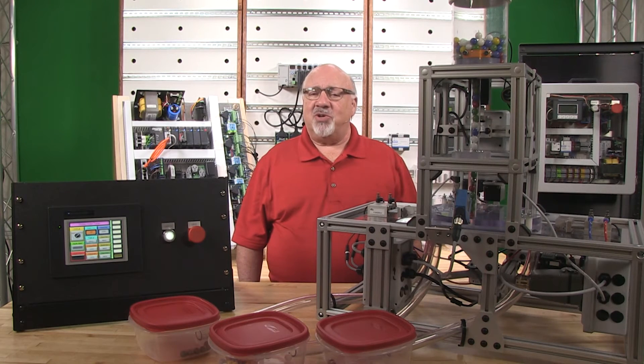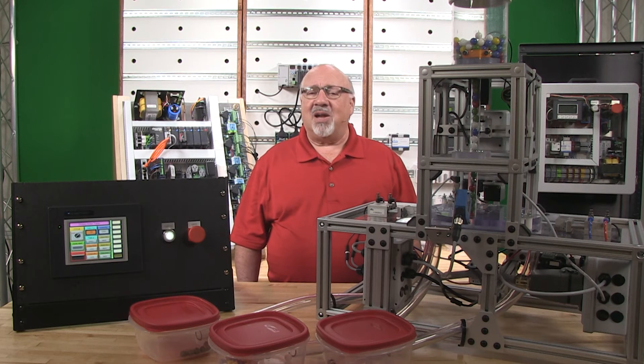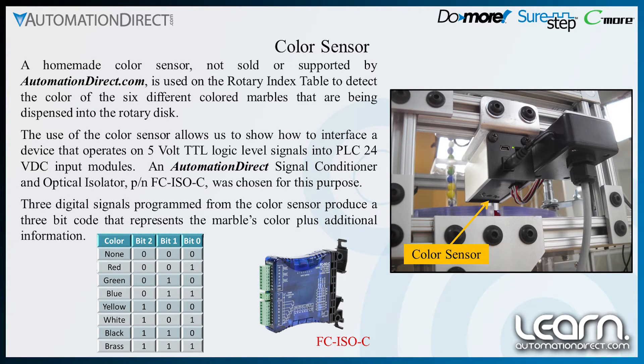The two reject slide cylinders used for the steel and brass balls are equipped with magnetic sensors actuated from the cylinder's magnetic piston. These sensors are used to determine the position of the slide cylinder. The cylinder fully extended sensor is used to make sure the reject gates are fully closed before allowing an index to occur. The cylinder fully retracted sensor is used to make sure the reject gate has made a full stroke. A homemade color sensor, not sold or supported by automationdirect.com, is used on the rotary index table to detect the color of the different colored marbles.